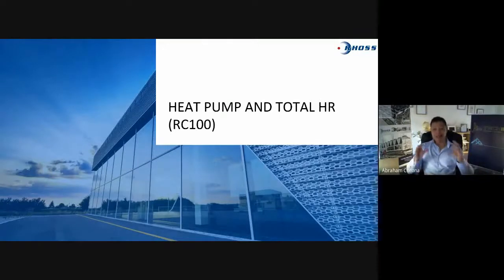All right. The critical bit is the data sheets are quite similar, 95%. So if you don't know what you're reading, you can be selecting a reversible heat pump with heat recovery instead of a 4-pipe in the data sheets. But the real disaster is going to be on site when you need independent cooling or heating, all right? Or vice versa. As I told you, if I need heating and I don't have a demand of cooling or heating in the primary circuit, I may not be able to get that heating.